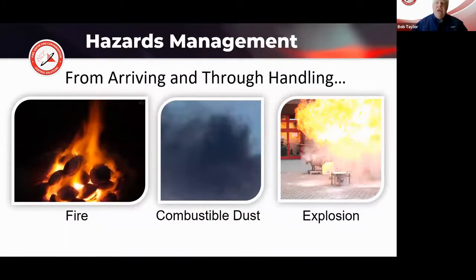As we look at hazards management, we begin to recognize that from the time material arrives at the facility through its handling to its final destination of conversion, the hazards often deal with fire and explosion, the two most likely things to happen at a steam electric generating facility. Most of them also involve a level of combustible dust, whether it's biomass, coal, rubber, or refuse, which brings an additional complicated hazard to the table.